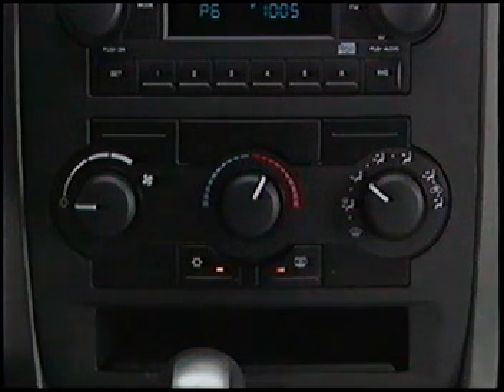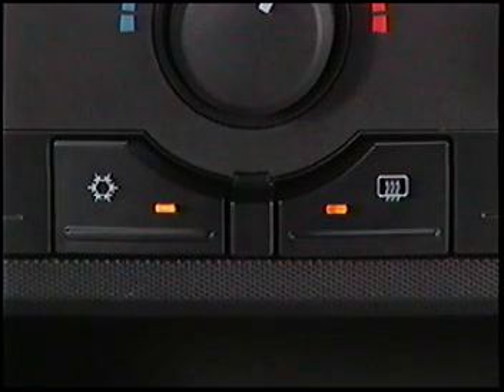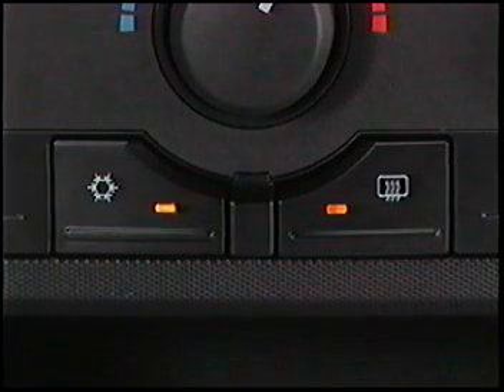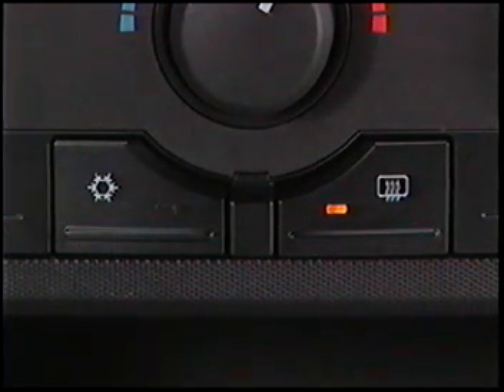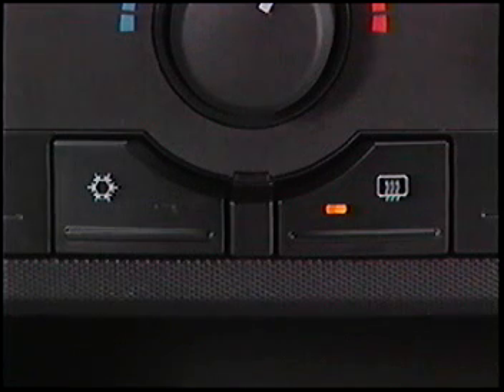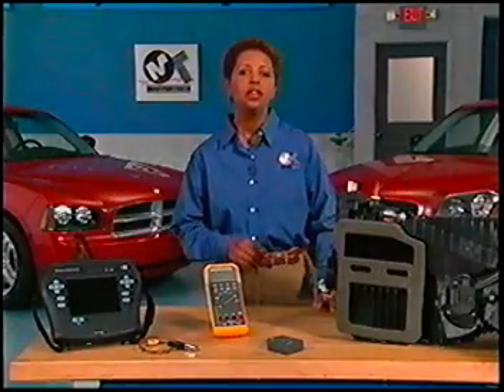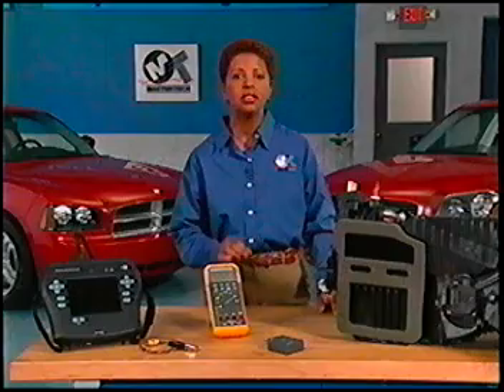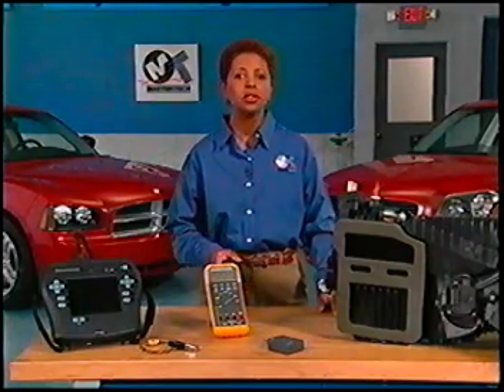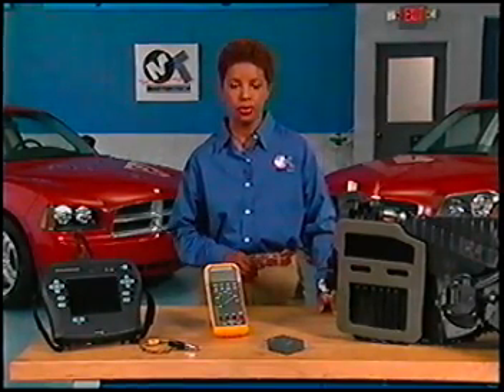The LEDs will illuminate for 5 seconds, and then the AC indicator LED will begin displaying trouble codes, if any are present. Long flashes of the LED indicate the first digit of the trouble code, while short flashes indicate the second digit. For example, here the trouble code is 34. Note that the EBL LED is illuminated for stored codes, but not for active codes. The control head displays trouble codes in ascending numerical order and will start over after displaying all codes.